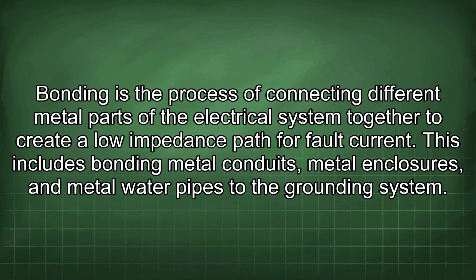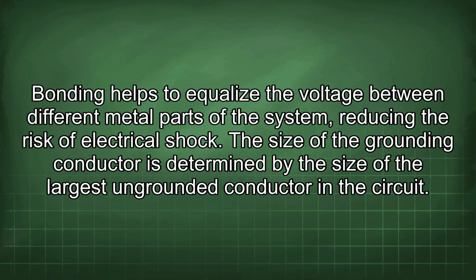Bonding is the process of connecting different metal parts of the electrical system together to create a low impedance path for fault current. This includes bonding metal conduits, metal enclosures, and metal water pipes to the grounding system. Bonding helps to equalize the voltage between different metal parts of the system, reducing the risk of electrical shock.